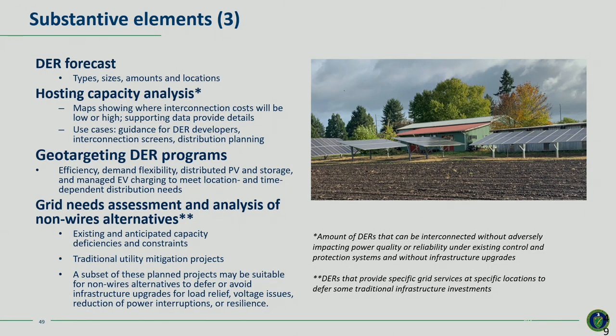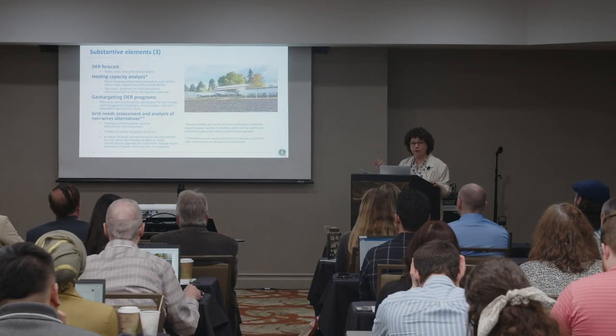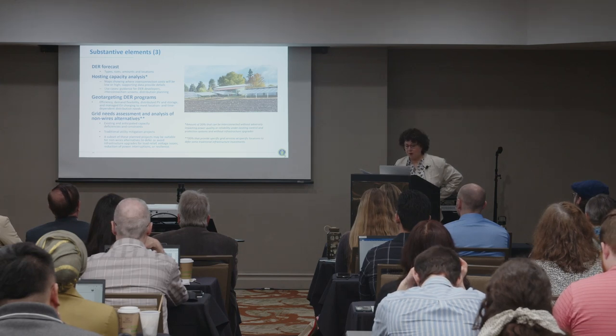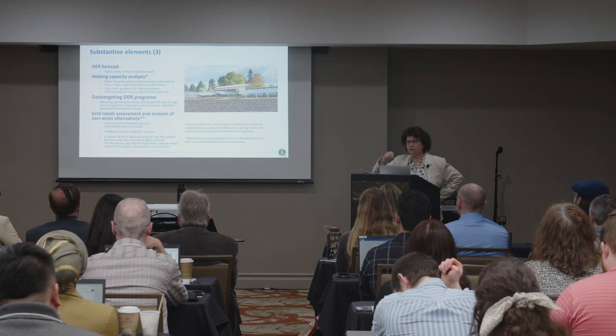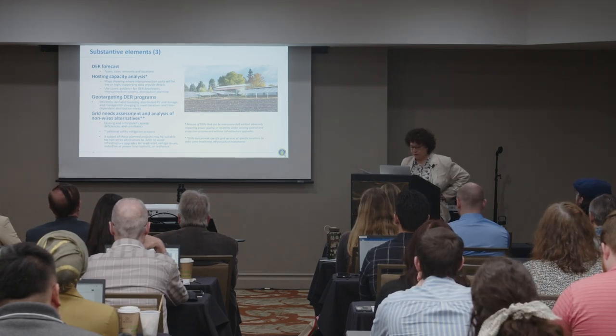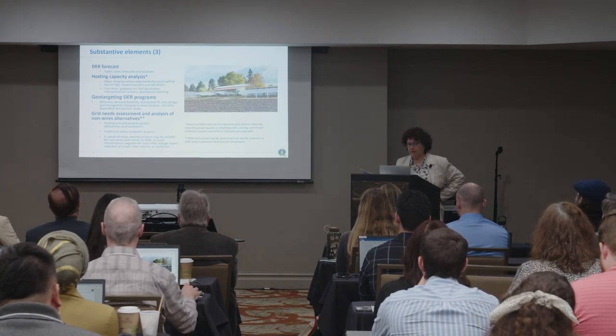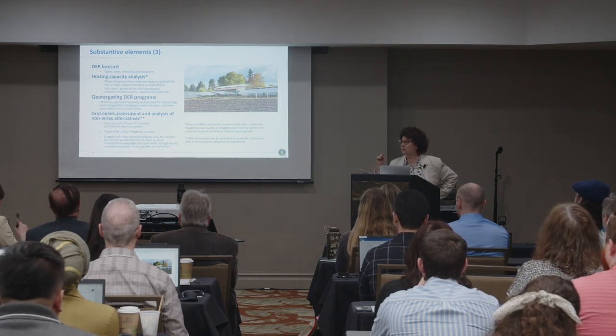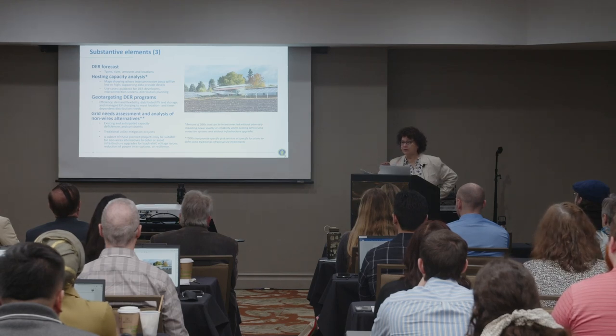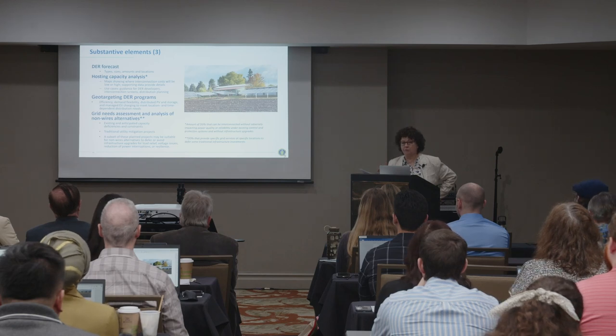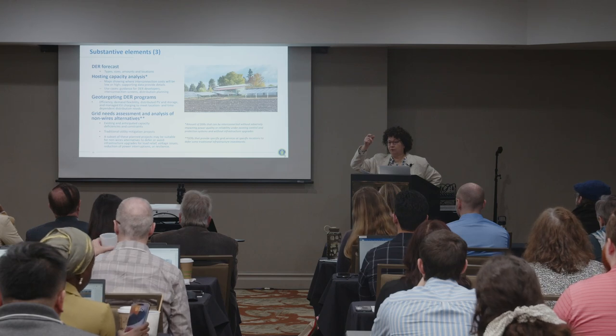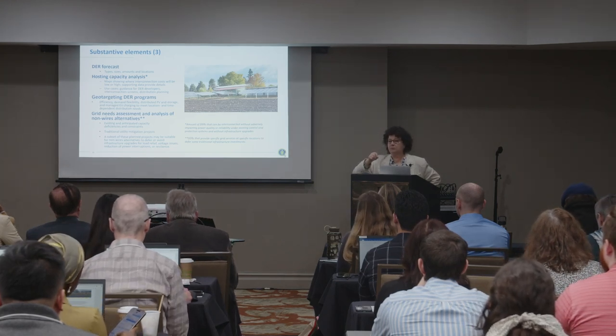Distributed energy resources are one of the drivers for states requiring utilities to file distribution plans. Forecasting distributed resources and assessing the distribution system's hosting capacity — the ability for the distribution grid at a particular spot to host additional solar or EV charging — are really important components of distribution planning today. I also want to highlight geo-targeting the programs that rate payers are already funding — efficiency, demand response, storage, solar — to test using those programs to help meet distribution needs, getting more bang for your buck by offering slightly higher incentives for resources that will help meet distribution system needs.